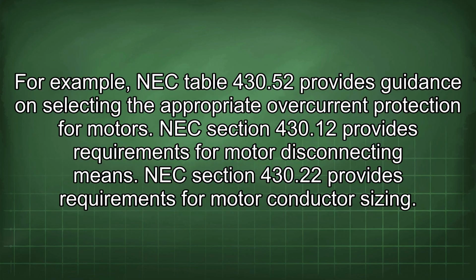For example, NEC Table 430.52 provides guidance on selecting the appropriate overcurrent protection for motors. NEC Section 430.12 provides requirements for motor disconnecting means. NEC Section 430.22 provides requirements for motor conductor sizing.